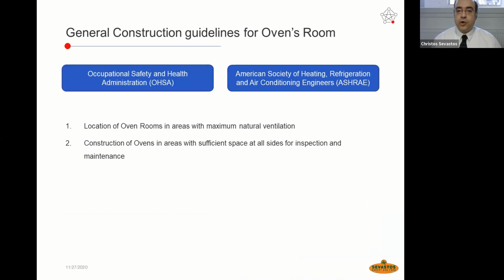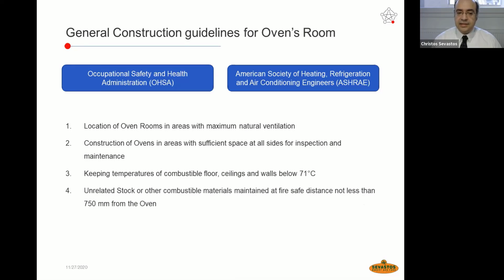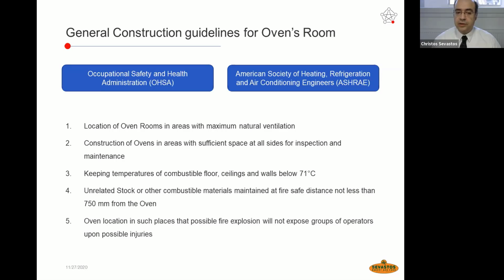General construction guidelines for ovens room by Occupational Safety and Health Administration and by American Society of Heating, Refrigeration and Air Conditioning Engineers. The location of the oven rooms should be in areas with maximum natural ventilation. The construction of the ovens should be in areas with sufficient space at all sides for inspection and maintenance. We must keep the temperatures of combustible floor, ceilings, and walls below 71 degrees Celsius. All unrelated stock or other combustible materials should be maintained at fire-safe distance not less than 750 millimeters from the oven. And of course, the oven location should be in such places that possible fire explosion will not expose groups of operators upon possible injuries. So those are the main guidelines which are manifested and which should be governing the whole design of your plant in terms of safety and of course in terms of efficiency.